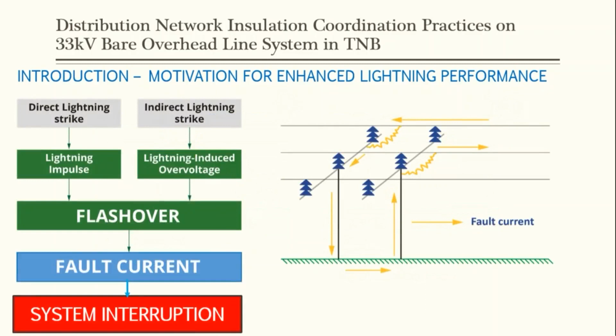Okay, and why do we need to really protect our system from direct lightning strike or even indirect lightning strike? For example, direct lightning strike will cause lightning impulse. Indirect lightning strike can cause lightning induced overvoltage. Both can cause flashover to the system, and because of the flashover, it will develop into fault current, and our protective system, our relays, for example, will see that as a fault, and due to that, there will be system interruption, and the supply to our customers will be disrupted. So we really need to look into this lightning performance to ensure that we minimize the system interruption or the interruption of supply to our customers.